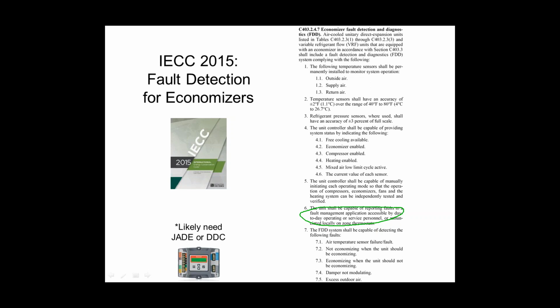In regards to responsibility for compliance, whoever is pulling and signing the permit, that would be my initial statement in general. If it's a big plan and spec job and there's a professional engineer involved, the professional engineer has to make sure that everything complies, or at least he has to tell people to comply, and hopefully they actually do it, right? If it's a small little rooftop change out from just a service contractor, an HVAC contractor, whoever goes down to the city office and fills out the permit application, that person needs to make sure that it complies. The controls contractor, assuming you have a DDC system, he may or may not be responsible. If the guy pulling the permit has outsourced the controls to the controls contractor and put in his contract to do certain things, then he would have to do those certain things, obviously. So the ultimate responsibility is whoever signs the permit and stamps drawings. Those are the people. But obviously you can sub some of those responsibilities out as needed depending on what you're trying to do. Sorry for the side tangent. I just thought it was a good question.